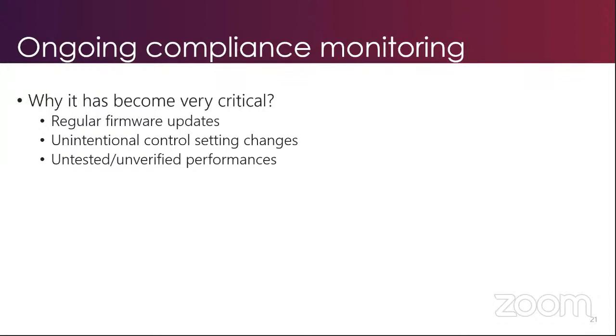And also there are a lot of changes, especially for solar, wind, or battery systems. The OEMs can push firmware upgrades quite regularly because they continuously improve their products. And sometimes there can be unintentional control setting changes, which mean the plant might not meet the grid code's requirements. And sometimes we cannot test everything during testing. We have to wait for a system event to get this information as well.